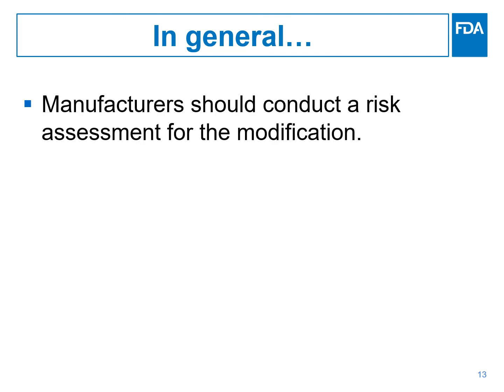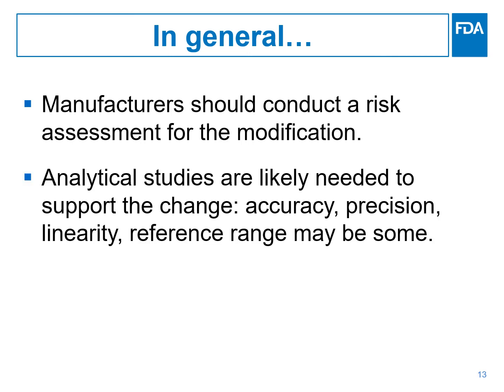As I just mentioned, creating a one-size-fits-all approach would be difficult, as the evidence needed to support a modification depends on how much the company needs to modify the assay in order to achieve standardization. However, we have some general concepts here. Per the quality system regulation and recommendations provided in the FDA guidances, manufacturers must conduct a robust risk assessment to guide their decisions regarding validation and verification activities to support the modification. We think it's reasonable to believe that the studies needed to support the change in standardization will be analytical in nature, and companies are very familiar with study design for those studies, which may include accuracy, precision, linearity, and maybe reference range studies.